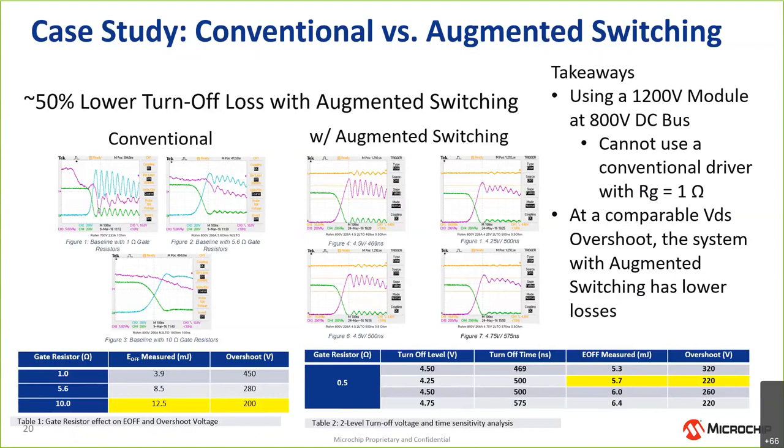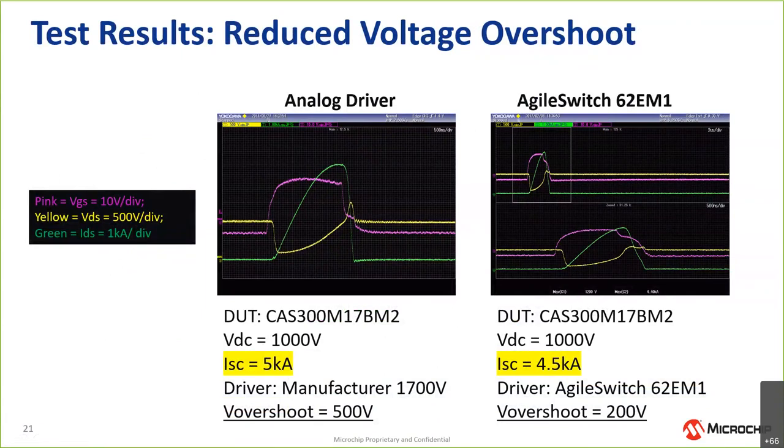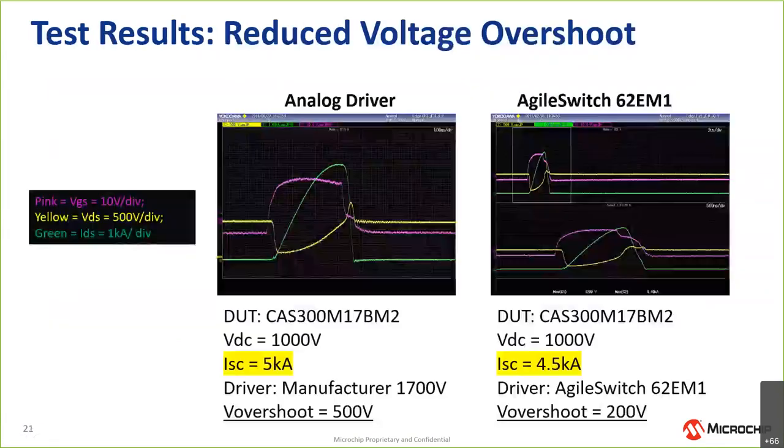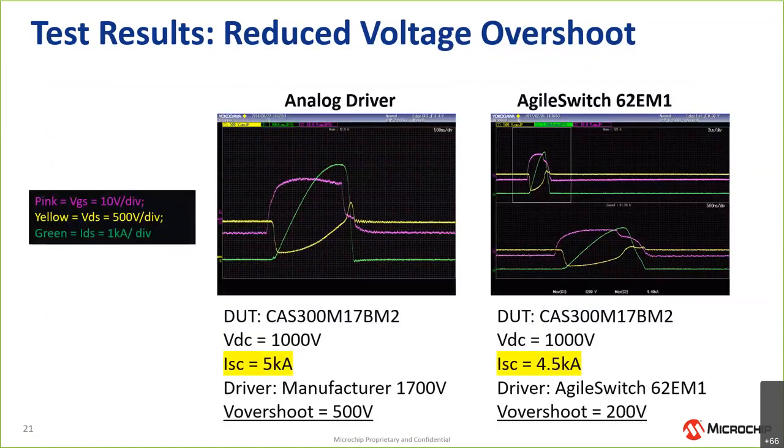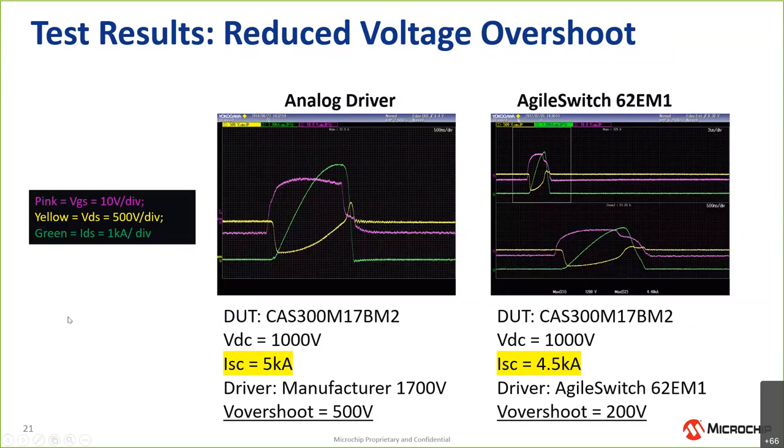We also took a look at overshoot very specifically. This was an example looking at a Wolfspeed 1700 volt, 300 amp module. In this instance, we were able, through modifying the augmented switching, to reduce the overshoot from 500 volts down to 200 volts. This is also an approach that you could use to perhaps feel more comfortable using a lower voltage rating, depending on your application as well, which can be another cost savings in your application.